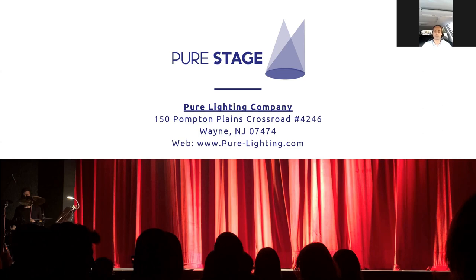All right. Next question, a technical one here: for LED lighting upgrades, does the controls infrastructure need to change? It depends. In most cases, yes. We're converting from either dimming halogen or incandescent lighting. In that case, there are dimming modules that will no longer work with LEDs. If a dimming module is connected to almost any LED light, almost any, there are some exemptions, you run a high risk of destroying the driver and making the unit obsolete and non-warranty. So in most cases, the answer is yes. Of course, an inspection is highly recommended, with a detailed breakdown on the state of their current system and what it would take to upgrade it to LED performance.